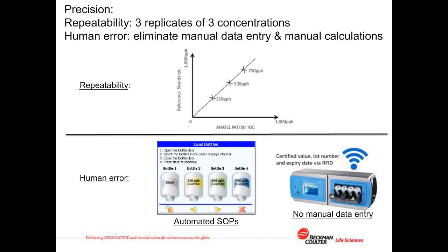The validation of analyzers for quantitation of impurities includes an investigation of precision. ICH Q2 recommends that precision of repeatability be validated using three replicates each of three certified standards at different concentrations. It also recommends that steps are taken to reduce the opportunities for human error to impact on optimal intermediate precision, such as automation of standard operating procedures and elimination of manual data entry and manual calculations.